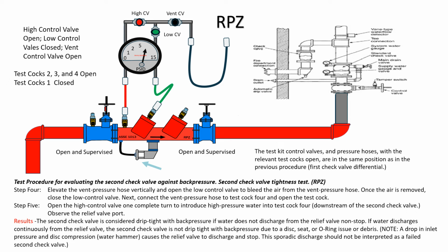Test procedure for evaluating the second check valve against backpressure. Second check valve tightness test. RPZ. The test kit control valves and pressure hoses, with the relevant test cocks open, are in the same position as in the previous procedure, first check valve differential. Step 4. Elevate the vent pressure hose vertically, and open the low control valve to bleed the air from the vent pressure hose. Once the air is removed, close the low control valve. Next, connect the vent pressure hose to test cock 4 and open the test cock.